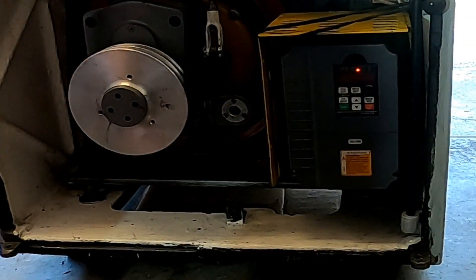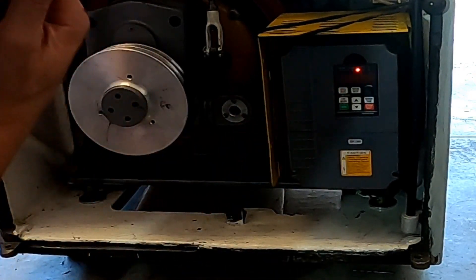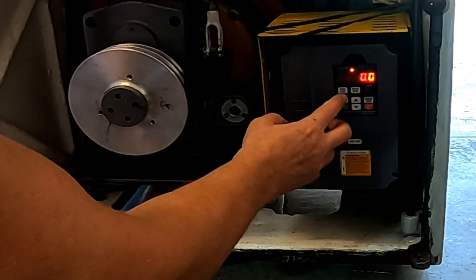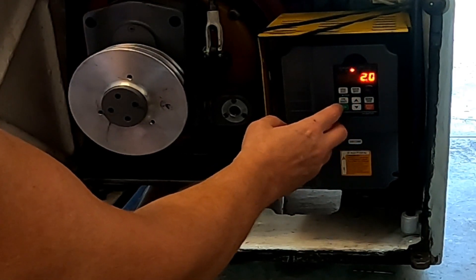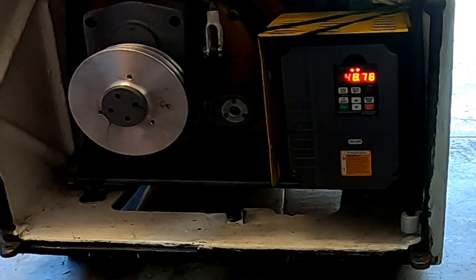That made it almost impossible for my ear, but I can still hear just a little bit of it. Probably if I put the covers back on I wouldn't hear anything. But let's go ahead and bring it up a little bit more — we can go all the way up to 15 with this. Bring it to Pd1, data set, going to go ahead and bring it up to 20. Data set, back out and see what happens.